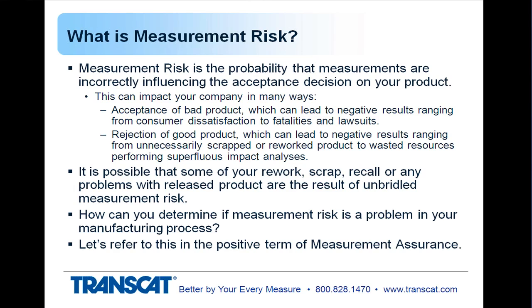So measurement risk is a probability that the instruments you're using and making decisions upon for your product are not what you think they are. That maybe those instruments are incorrectly influencing that acceptance decision of your product. So if you're accepting bad product, that can lead to negative results ranging from simple consumer dissatisfaction to something more extreme like fatalities and lawsuits. But if you're rejecting good product, that can lead to negative results as well. Possibly unnecessarily scrapping work, parts, components of your product, or reworking those components of your product, and that's wasted resources, as well as evaluating out-of-tolerance results and having to use your resources for that function.